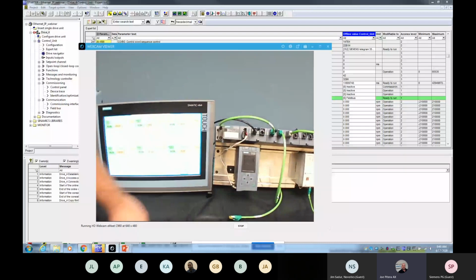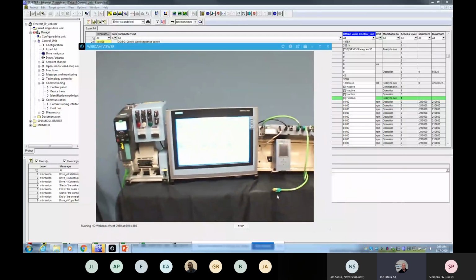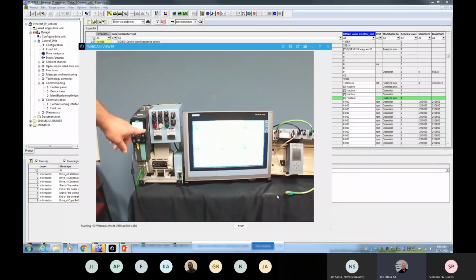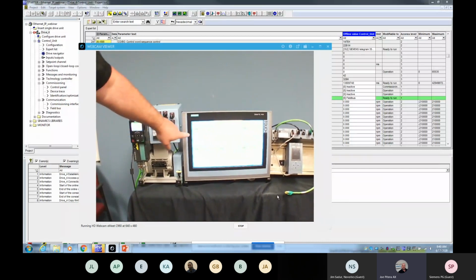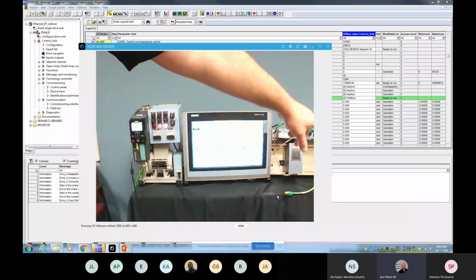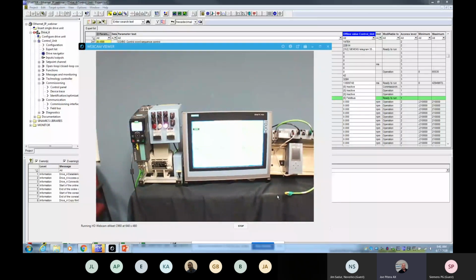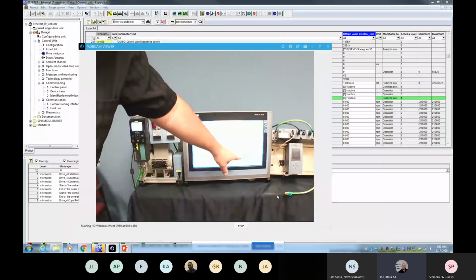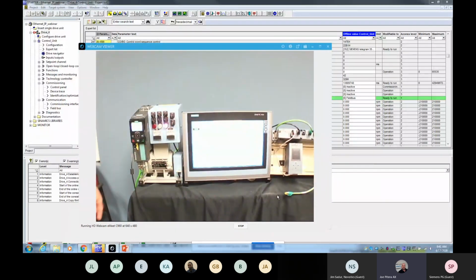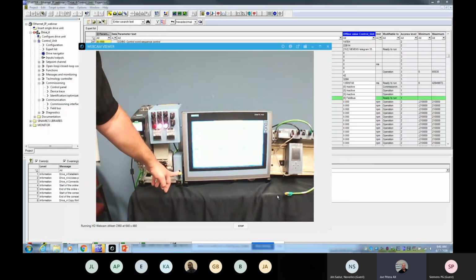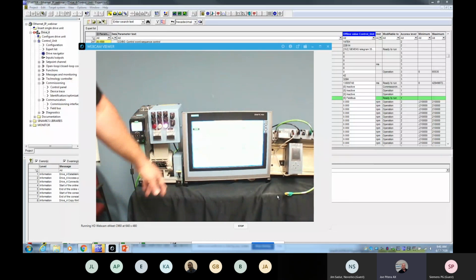I'm going to go to the EtherNet IP screen, and you can see that the drive is now happy and ready to communicate. I am going to hit the run, and it is now communicating Ethernet IP to the Rockwell PLC to the Siemens drive. And we can change the speed set points. And we see that we can get the alarms as well coming out of the drive over Ethernet IP. So one drive, you select the PLC. It makes it that easy.